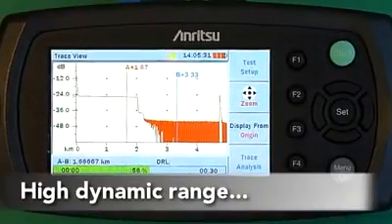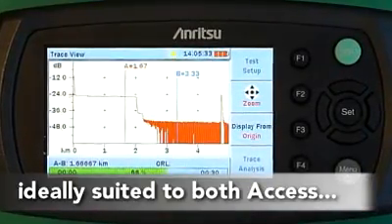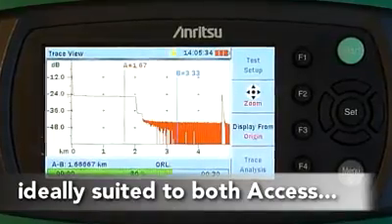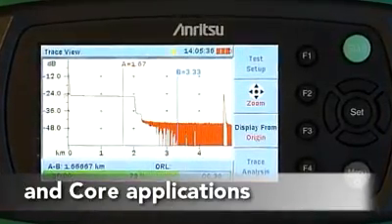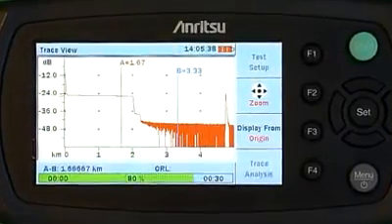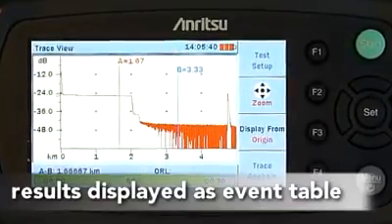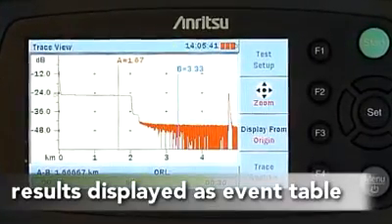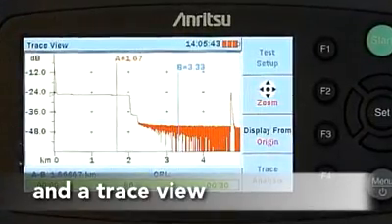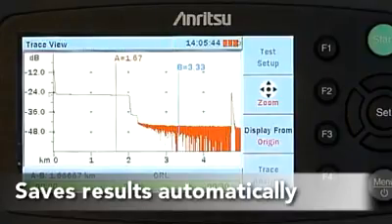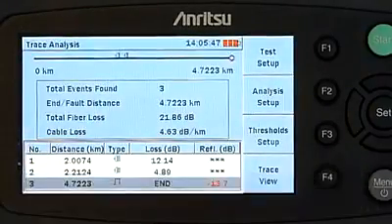With a dynamic range of 37 dB, it is ideally suited for both Access and core applications. It displays the results both as an event table and in trace view, and results can be saved automatically using file names you choose.